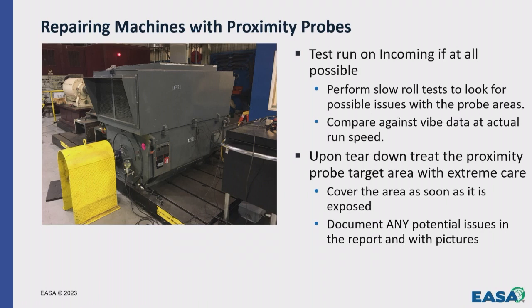And when you tear down this motor, treat the proximity probe target area like mom's fine china, the most valuable thing in that motor. Even hairline scratches will greatly affect the accuracy and can cause you to fail on the back end. So cover that area as soon as you can. The guys in the shop, none of them like it when we stand over their shoulders, but this is the appropriate time to stand over their shoulder. Make sure, until they understand exactly how critical that area is, that they're covering it and taking care of it. Take lots of pictures, document everything related to that probe target area.